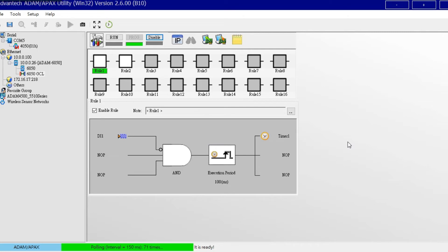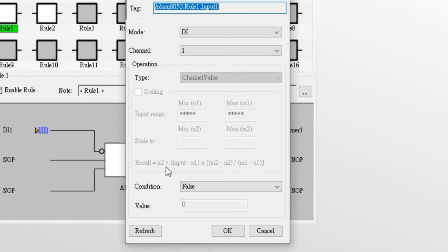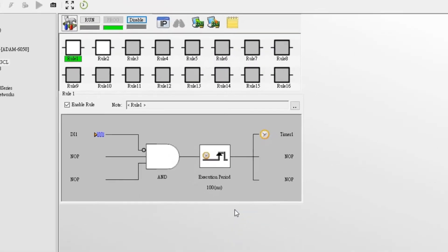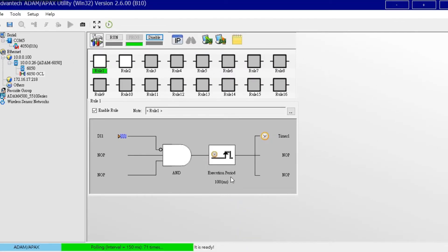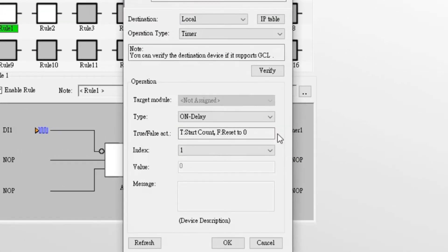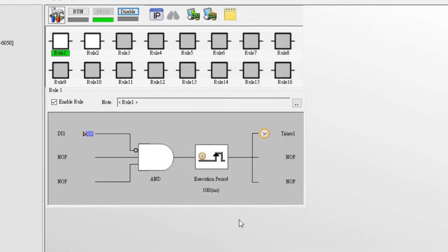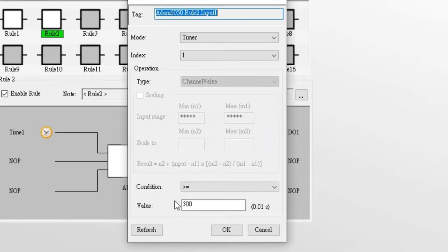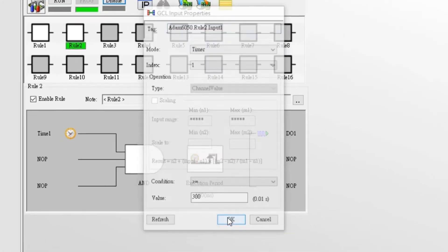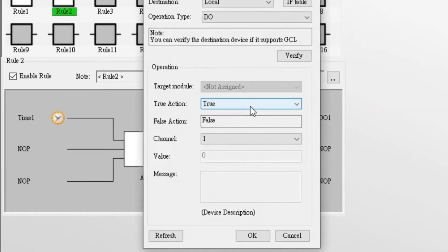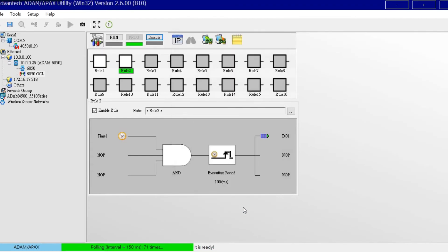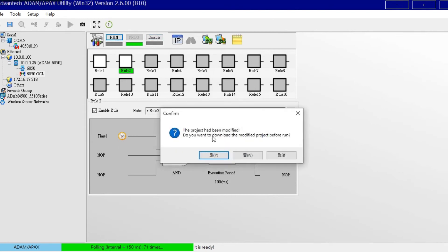Let's start with the first example using Adam 6050. We want to achieve: when digital input channel 1 gets logic low, then digital output channel 1 will get logic high after 3 seconds. In logic row 1, we select DI channel 1 as the input condition, with the condition set to false to trigger row 1. For the logic gate, we select AND gate, execute at 100 milliseconds, then trigger timer 1 to do an on-delay. In logic row 2, we set timer 1 as the input condition — when the timer value equals or exceeds 3 seconds, it will trigger DO1. The output true action turns on when receiving logic true. After setting the rows, we download the GCL rows to ADAM and run the GCL project.